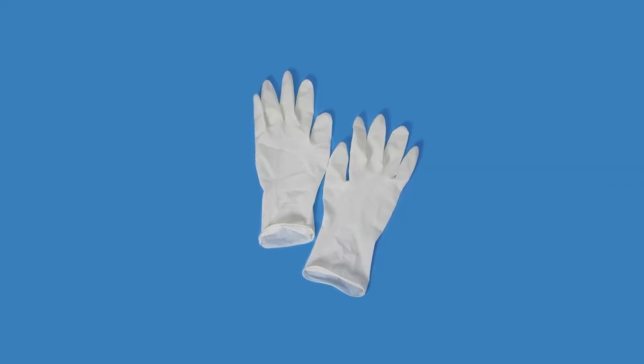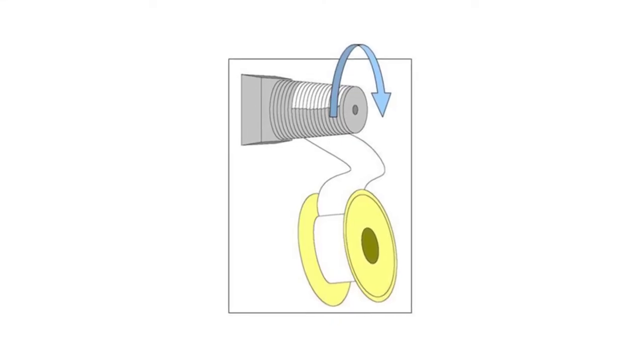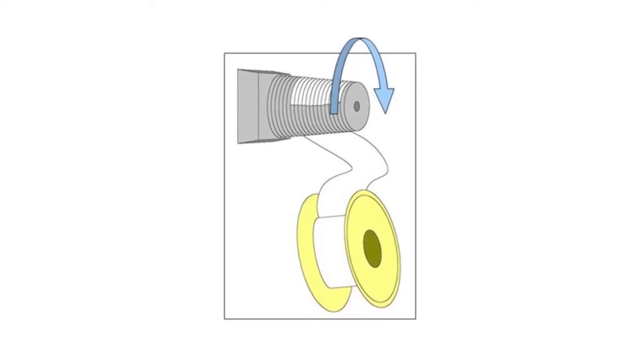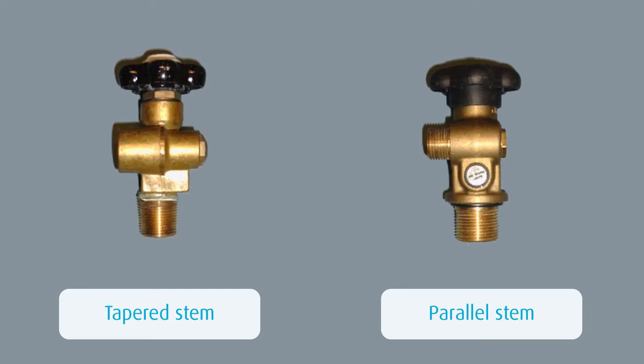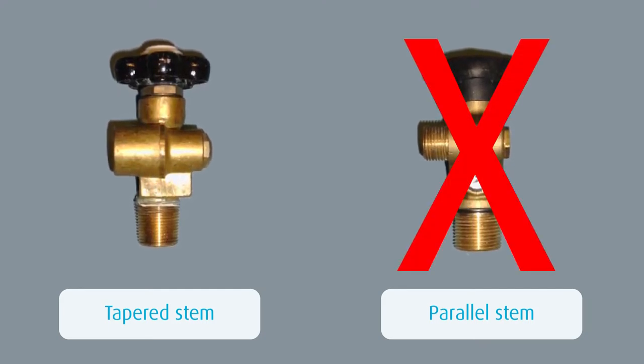Before performing taping, personnel should wear latex gloves. Tape application is only required for tapered threads. It is not applicable to straight or parallel threads, which use a gasket to create a seal.